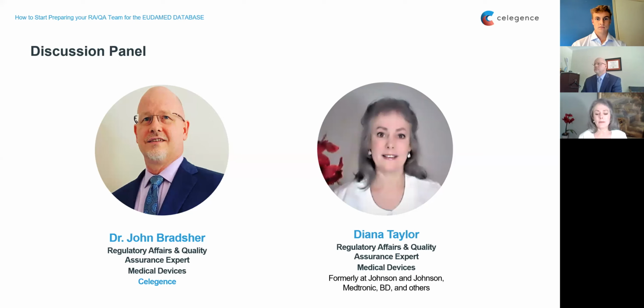And as John mentioned, software as a device will also have some additional requirements for what will require an update on your UDI. So any changes that are going to impact the performance, safety, or interpretation of the data for your software device, any changes to the user interface language, and again, any changes that could lead to a misidentification of a device or any ambiguity in their traceability, you'll need to update your UDI.